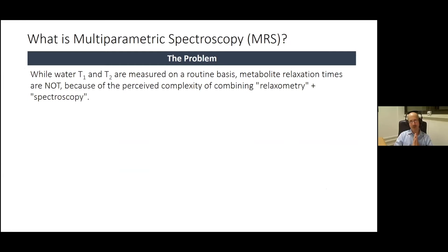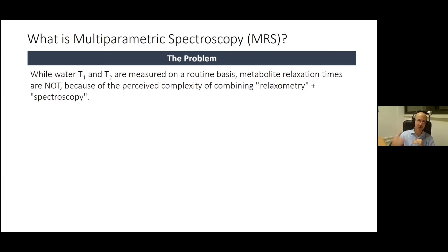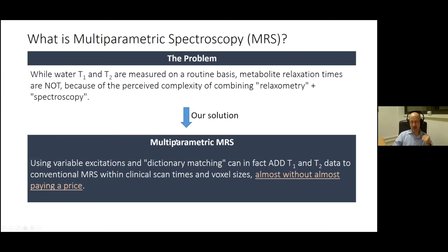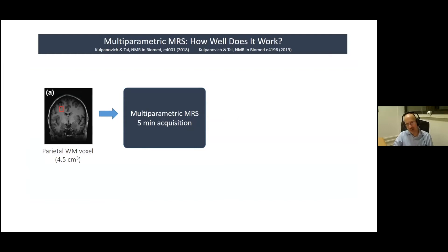The conventional problem is that both measuring relaxation times (relaxometry) and doing spectroscopy are perceived as complex and time-consuming. People don't do this routinely, and when they do it's usually prolonged inversion recovery or multi-echo experiments with many time points. Our multi-parametric approach — using variable excitations and dictionary matching — shows that we can measure relaxation times in addition to concentrations within the same clinical scan times, the same voxel sizes, and without almost paying a price in sensitivity.